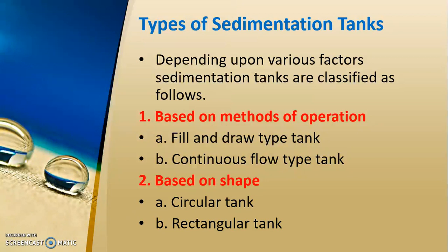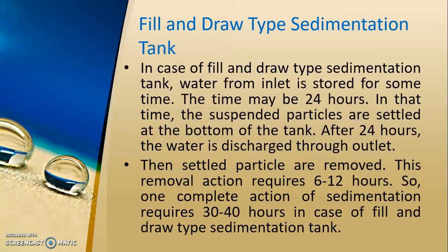Sedimentation tanks are of different types. Based on the method of operation, there is the fill-and-draw type and the continuous flow type. Based on shape, there are circular and rectangular tanks. In the fill-and-draw type, water is stored in the tank for a detention period — typically 24 hours — during which suspended particles settle at the bottom, then water is discharged through the outlet. However, since this type requires many tanks, which is not feasible for a water treatment plant, it is not commonly used.